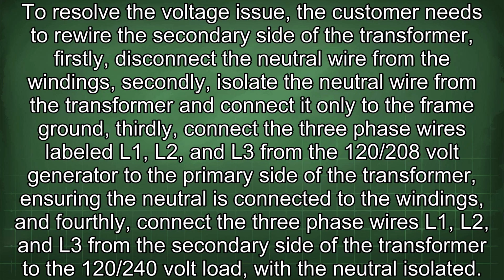To resolve the voltage issue, the customer needs to rewire the secondary side of the transformer. Firstly, disconnect the neutral wire from the windings. Secondly, isolate the neutral wire from the transformer and connect it only to the frame ground. Thirdly, connect the three-phase wires labeled L1, L2, and L3 from the 120/208 volt generator to the primary side of the transformer, ensuring the neutral is connected to the windings.